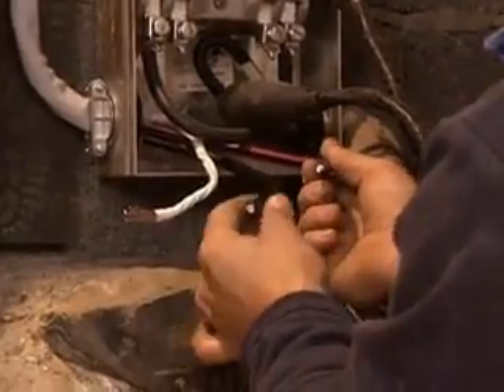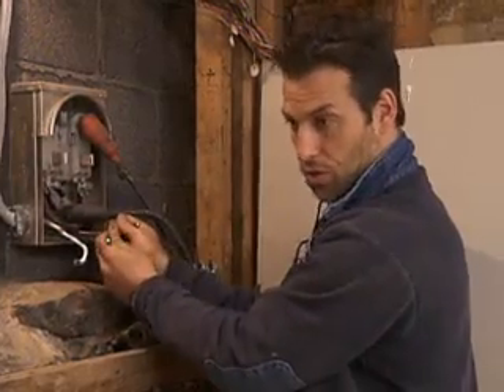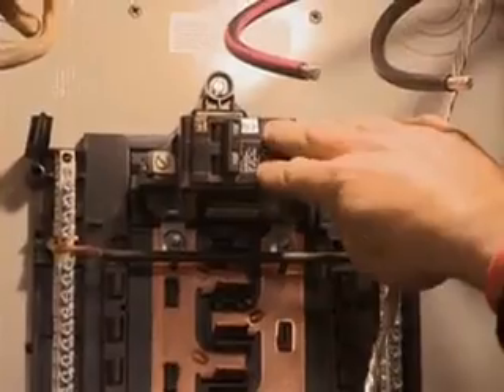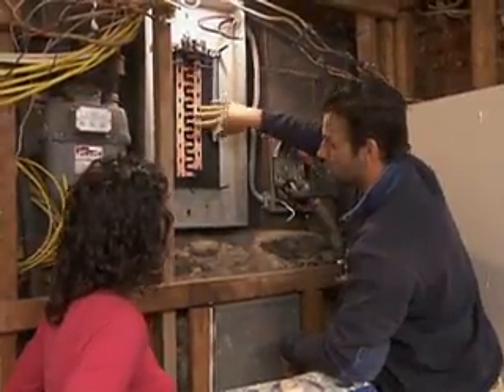So you have a red wire and a black wire. These are your 2 hots. This is what gives you 220 volts. Once these heavy lines go in here, it breaks down and goes into the individual breakers, and then it leaves all the branch circuits, which are all the smaller wires.